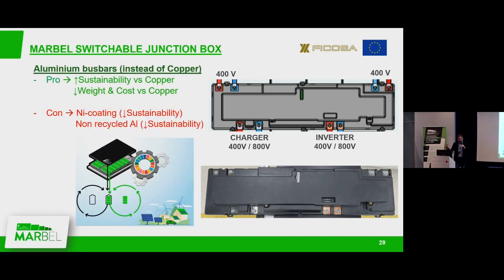We can decrease the weight of the busbars by 50% going from copper to aluminum. Obviously aluminum has lower conductivity than copper, so you have to increase the section for the conductivity to be the same, but comparing apples with apples, we can decrease the weight of the busbars by 50% going from copper to aluminum. But what's the drawback?